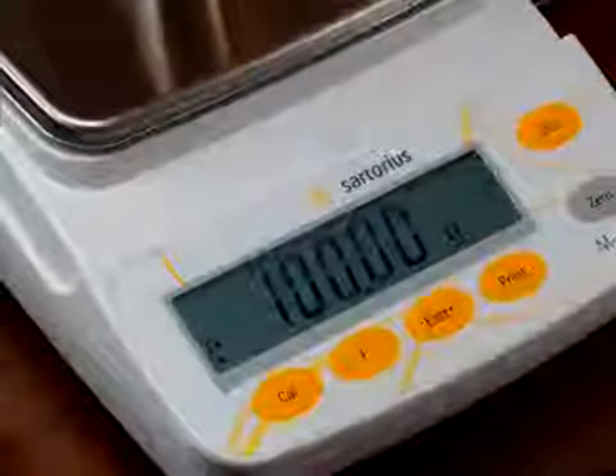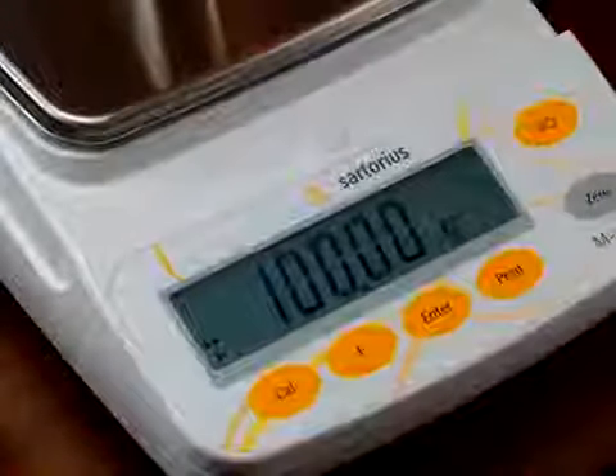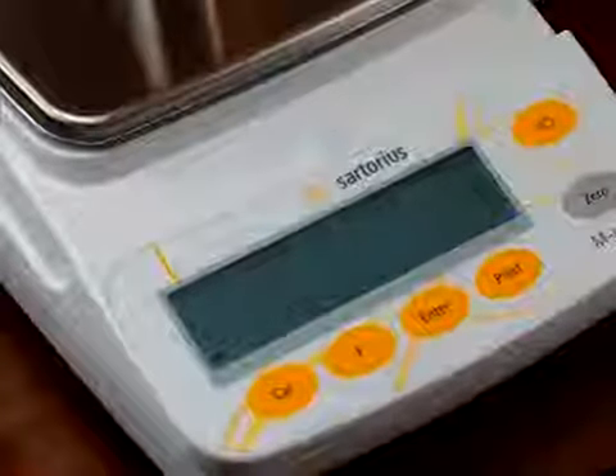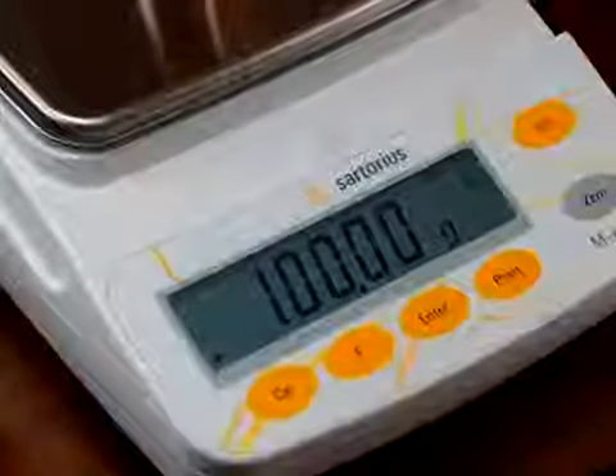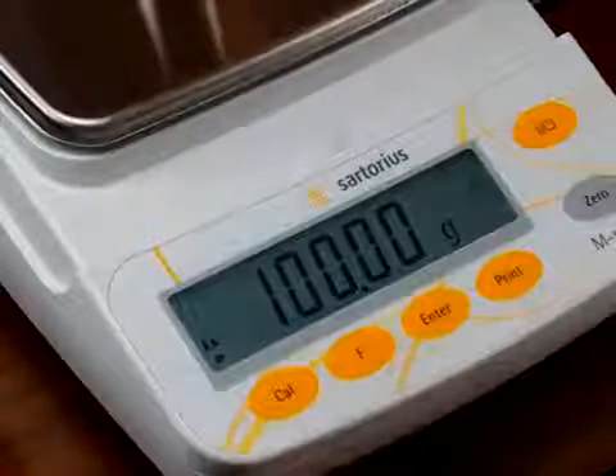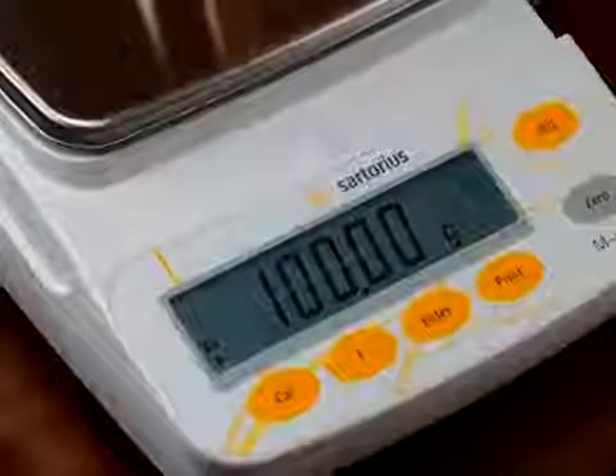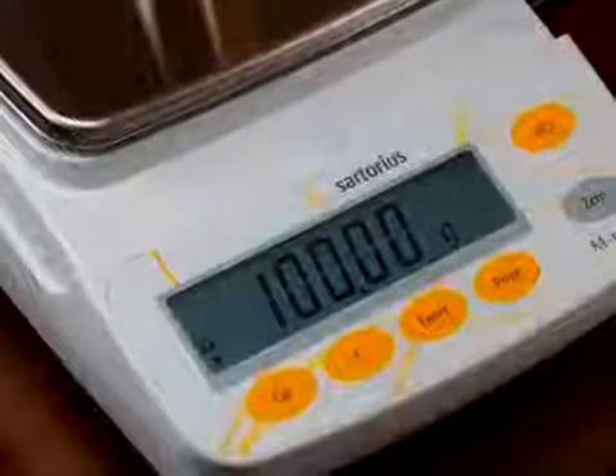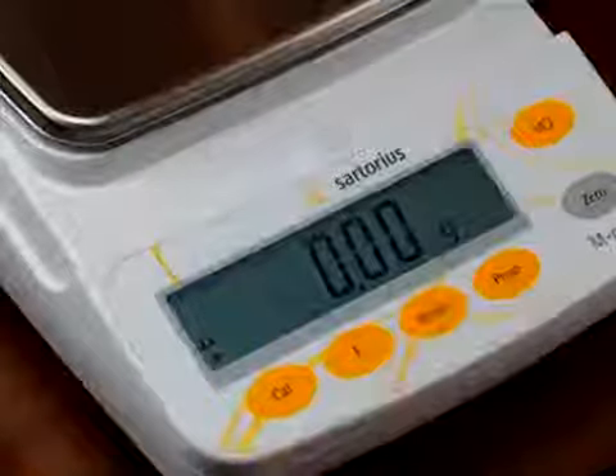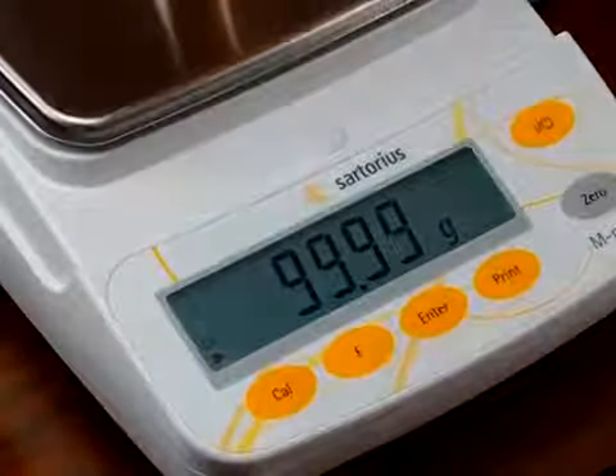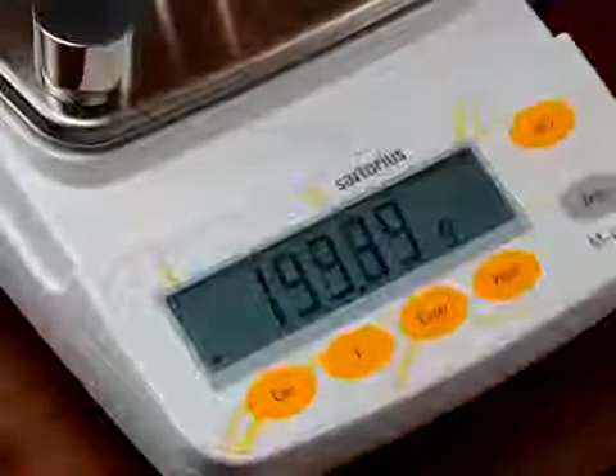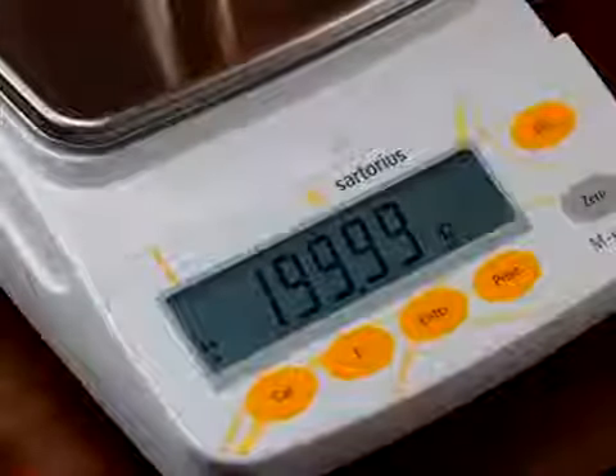The balance is just flashing 100. It's looking for the weight, and there's 200 grams on it. Therefore, it's rejected it altogether. Now if I remove the other 100 gram, you'll notice the balance flashes, and then it stops, so it stores it. And over here on the left-hand side, you'll see the stability symbol. So we know this balance has been calibrated. If we take the weight off, we can put the weight back on. We can put the other weight on. And you can see the balance is now calibrated.